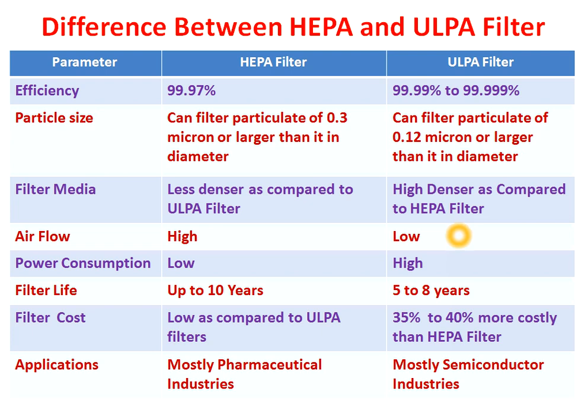Due to the greater pressure drop, the air passing through the ULPA filter is much less. Now for power consumption: the HEPA filter has low power consumption because its less-dense filter media places less load on the blower. In contrast, the ULPA filter has high-density filter media, which puts more load on the blower and results in higher power consumption.